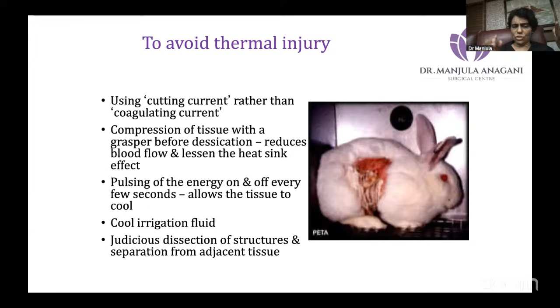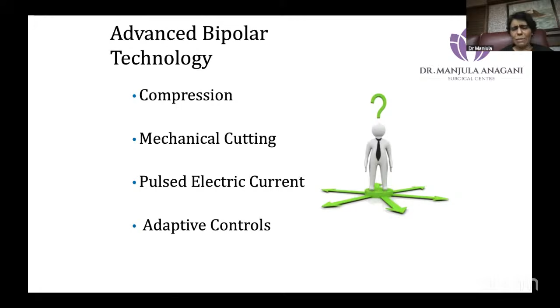So what is advanced bipolar? The difference is that compression is done by the generator or by the instrument. Mechanical cutting is what we do with traditional; here the cutting is done by the instrument. Pulsed electric current is delivered by the instrument here, whereas in traditional we have to do it ourselves. Adaptive controls, where everything stops at 100 degrees, are handled by the instrument or generator, whereas by using the pulse technique we will stop at 150 degrees. So we can make our traditional bipolar into advanced bipolar.